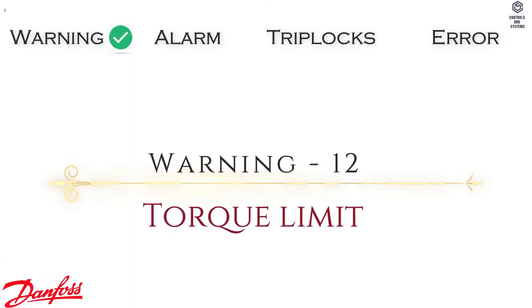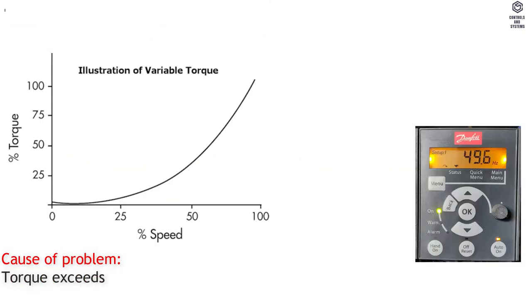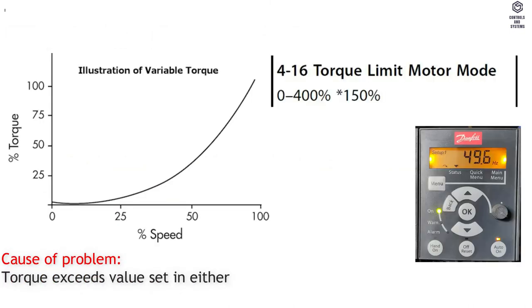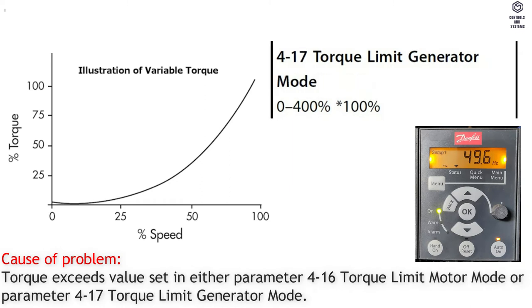Warning 12: Torque Limit. Cause of Problem — torque exceeds the value set in either Parameter 416 Torque Limit Motor Mode or Parameter 417 Torque Limit Generator Mode.